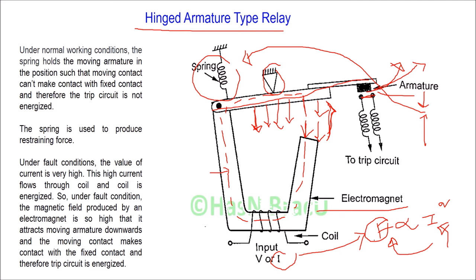During fault condition, the value of current will be high. If the operating force is high, then this moving armature will be moved downwards, and the moving contact of the moving armature will get connected with the fixed contact. When the moving contact and fixed contact get connected, the trip circuit will be closed. The energized trip coil will further open the moving contact of the circuit breaker. This is how a hinged armature type relay works.